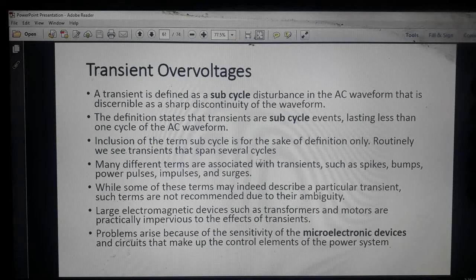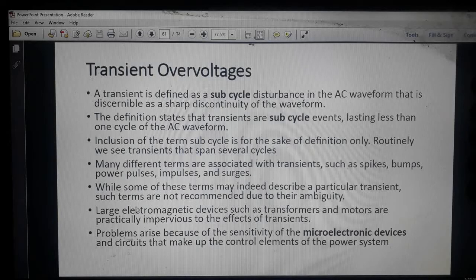It is not fixed for one cycle. It may be that this type of event happens over many cycles in the voltage waveform. Many different terms are associated with the transient, such as spikes, bumps, power impulses, and surges. These are the terminology used for transient over voltage. While some of these terms may indeed describe a particular transient, such terms are not recommended due to the ambiguity.